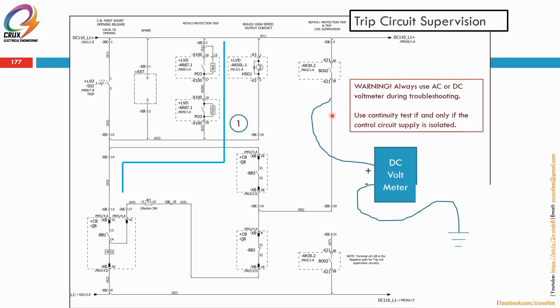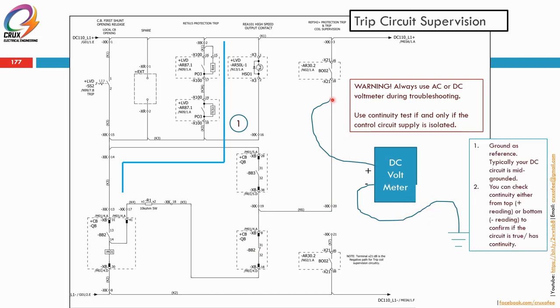Okay, so let's say that we want to check the healthiness of this coil under the breaker open condition. Actually, you can check. Under the breaker open condition, the tripping coil is connected to the negative, then going through a resistor, then going through this normally close contact. So if you measure from here to the ground, using ground as a reference, and assuming that the DC is a midpoint grounded, if it's a positive supply coming, you will measure plus 55 volts. If it's a negative supply coming in, it will be a measurement of negative 55.